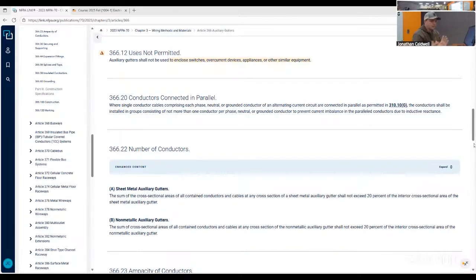But when you have parallel runs, the reason why you don't separate the phasing, so if you have a parallel run of two, you don't put A and B in one conduit and then C and a neutral in another conduit. It's because you're going to have magnetic force between those conduits that twists around, and you'll have weird inductance and reactance and all that. So that applies to gutters, right? So when you do your parallel, you don't want all your A phases together, all your B phases together, and all your C phases together inside a gutter.